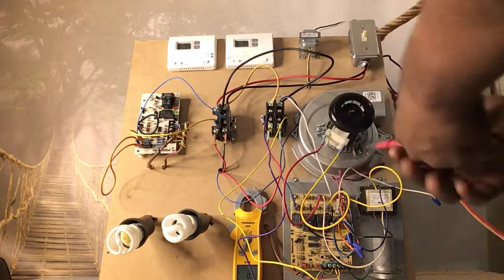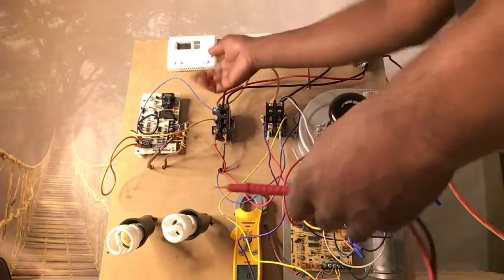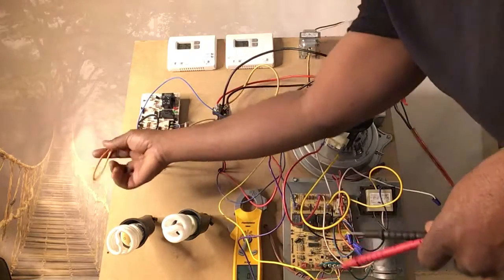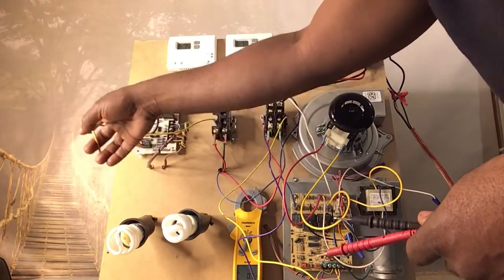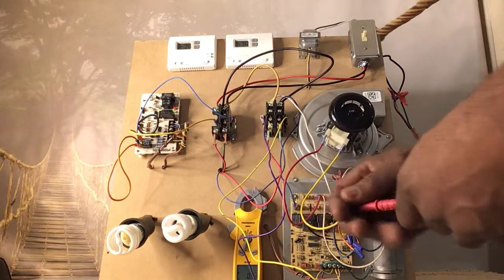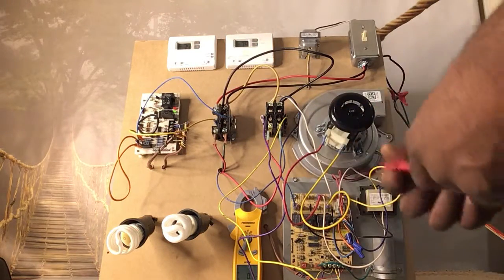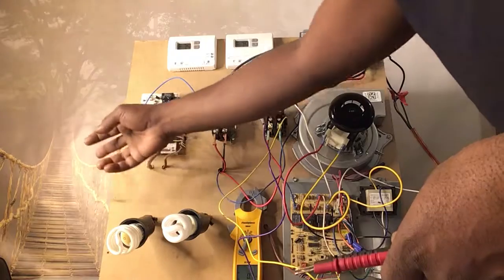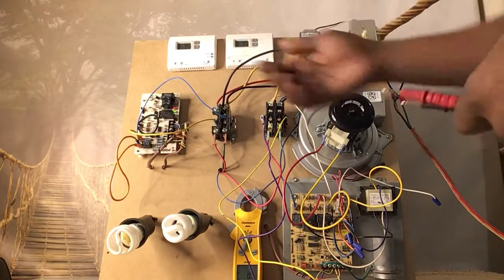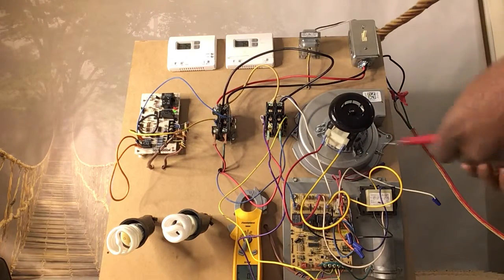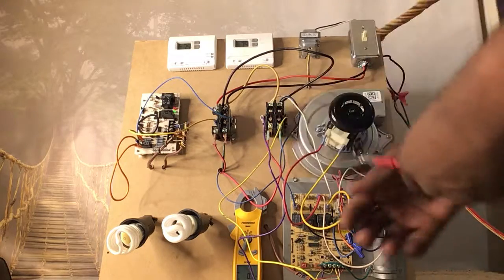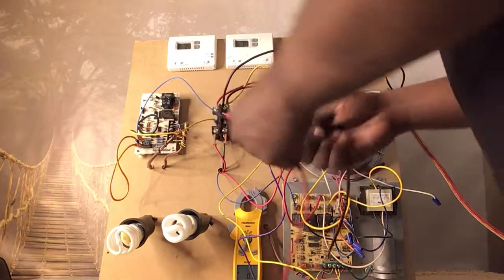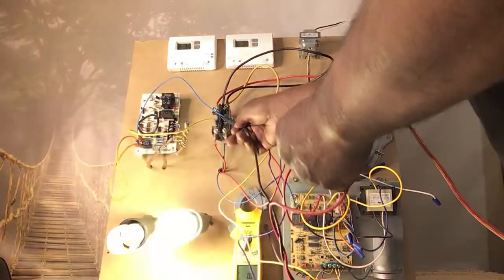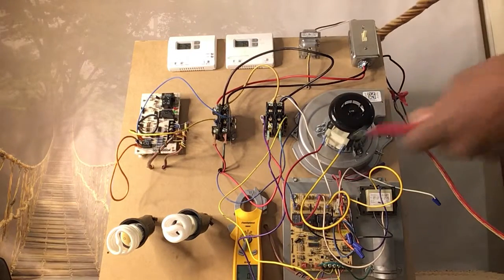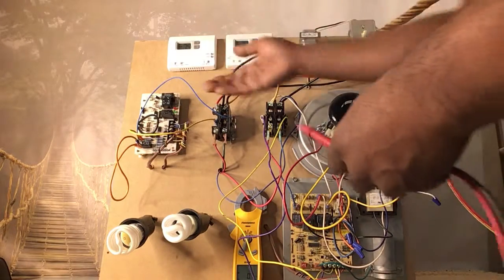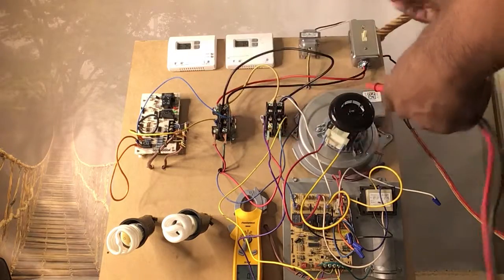This particular control board, the defrost control board, just for testing purposes, has low pressure switches that we have jumped out to simulate that the unit has good pressure. So it's a low pressure switch and a high pressure switch that we have jumped out, and those are some of the things you'll run into with systems that are low on freon. So you'll be trying to figure out why there's no power or why your contactor is not pulling in after you have asked it to come on. It's because you have run into some type of fault elsewhere, but you don't pass any steps.